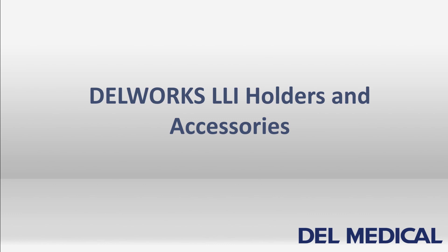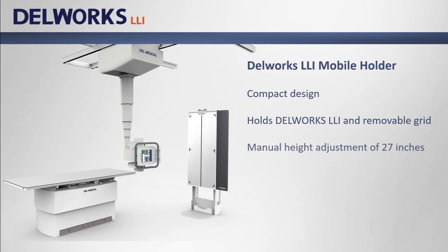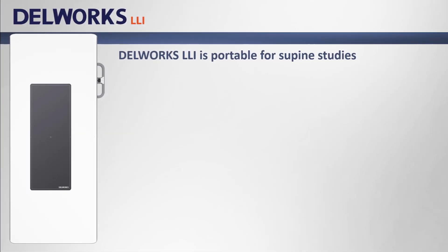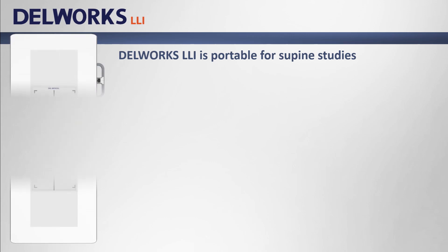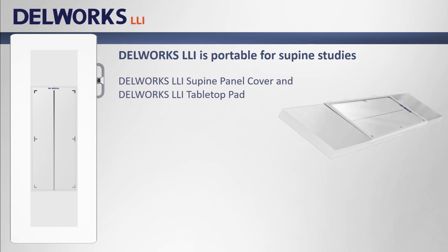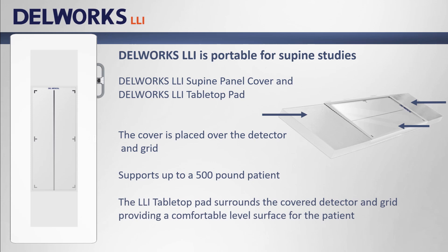DELWORKS LLI is available with multiple holders and accessories. The DELWORKS LLI mobile holder has a compact design, holds both the DELWORKS LLI detector and a removable grid, and has a manual height adjustment of 27 inches that can be lowered all the way to the floor — so for many patients hip to ankle studies can be performed without any additional step. It has concealed wheels so it can be easily tipped and moved out of place when not in use. For supine studies, the optional supine panel cover is placed over the detector and grid, supporting up to a 500 pound patient, with the LLI tabletop pad surrounding the covered detector to provide a level surface for the patient's upper and lower body.